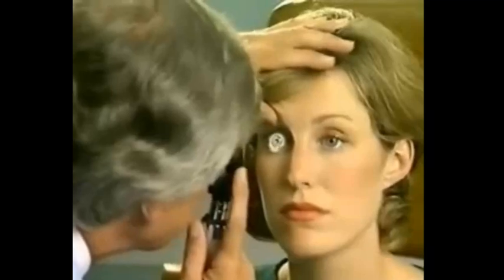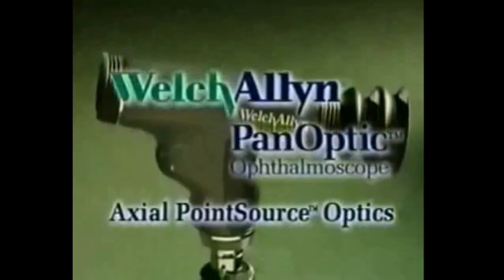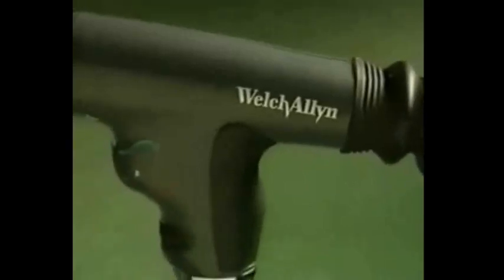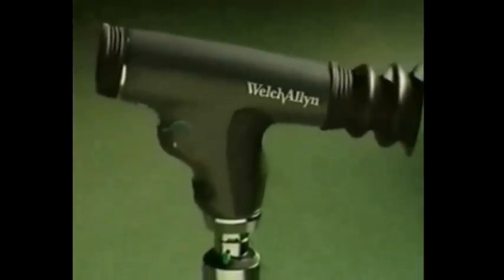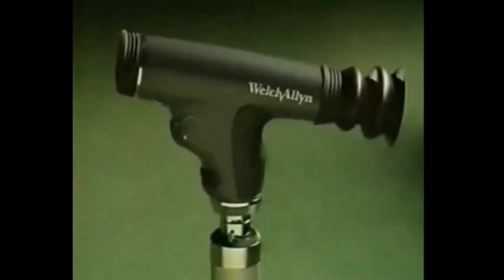Fundamentally, the technology and optical design of the ophthalmoscope hasn't changed in decades — until now. The Welch Allyn Panoptic is a revolutionary new concept in ophthalmoscopy. Developed and patented by Welch Allyn, the originator of the world's first handheld direct illuminating ophthalmoscope, the Panoptic incorporates an innovative and patented new optical design called Axial Point Source Optics. This enabling technology makes it easy to enter small pupils and provides a dramatically wider, more panoramic view of the fundus than ever before achieved with a standard ophthalmoscope in an undilated eye.